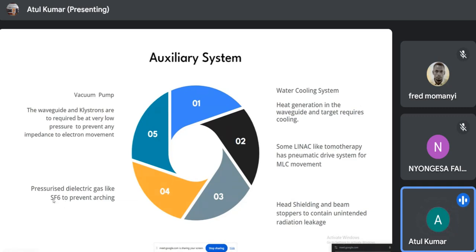You have to have water cooling systems around, because this LINAC heats up. Of those electrons and klystrons that we talked about, only 35% of the energy is turned to RF wave, and the remaining 60 to 65% is converted to heat. The same thing happens to the anode. When Bremsstrahlung production happens, only 0.1%, or in high energy LINACs maybe 5 to 6%, 8%, is converted to X-rays, and 92% or more is converted to heat. So to cool that anode and several other things, you need a cooling system. You need a pneumatic drive system if it is a tomotherapy, or a motorized system if it is a normal LINAC. You need head shielding and other things to prevent radiation leakage. So there are several other auxiliary systems attached to the LINAC.